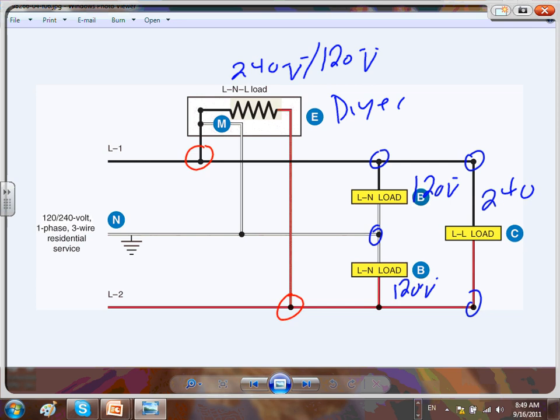If I take you to a house right now, would you be able to wire based on this? First, look at a piece of equipment. Is it 120? Grab one hot and a neutral. Is it 240 only — like heaters or air conditioning? Just two wires. Does it need 240 as well as 120? Then that's a typical dryer or range — three conductors with a ground.